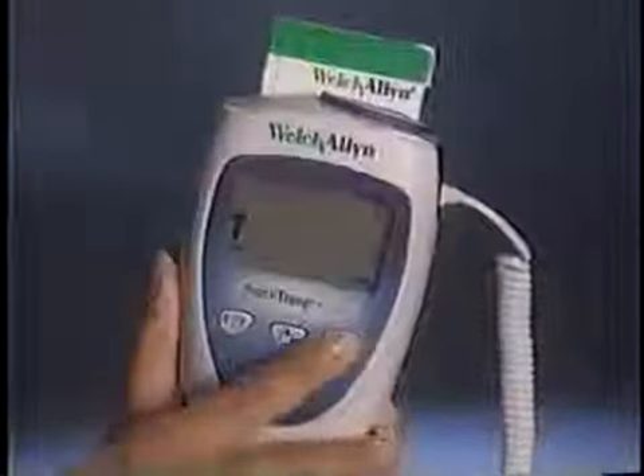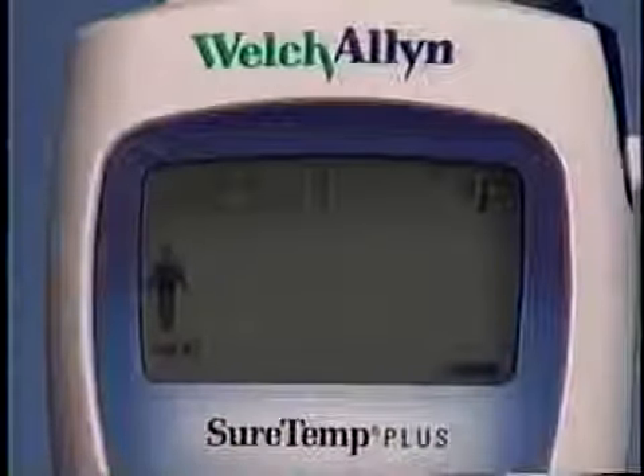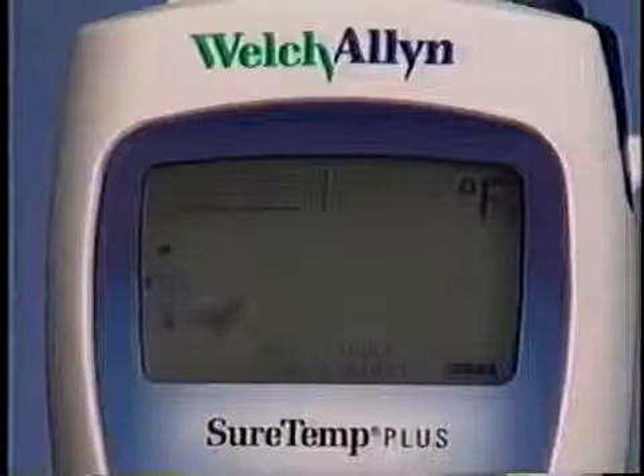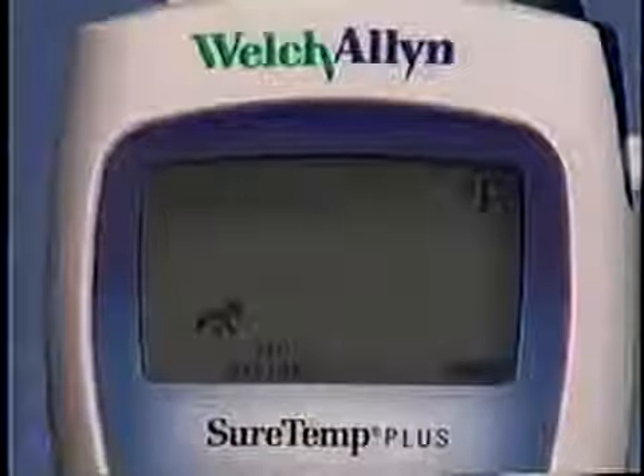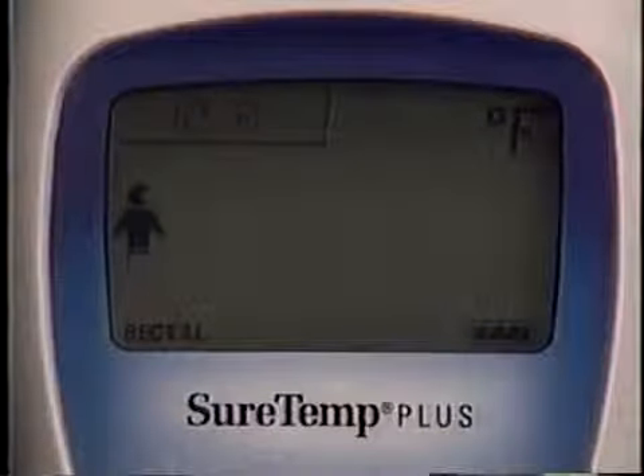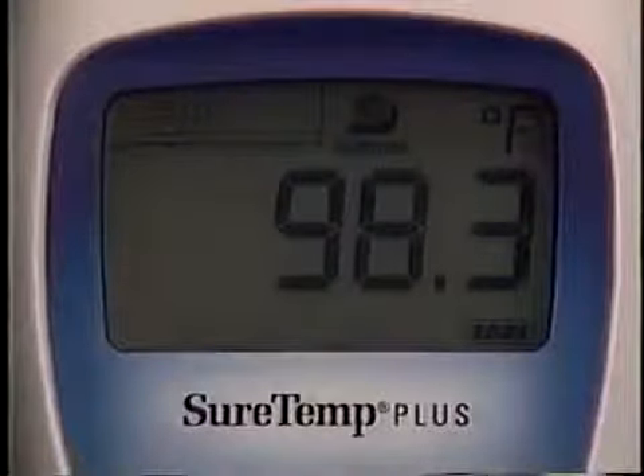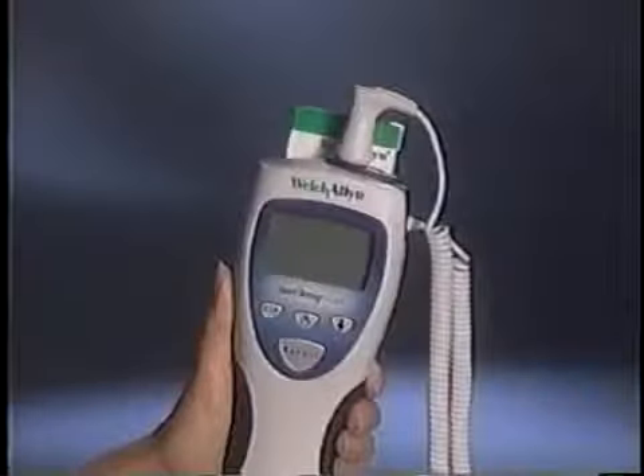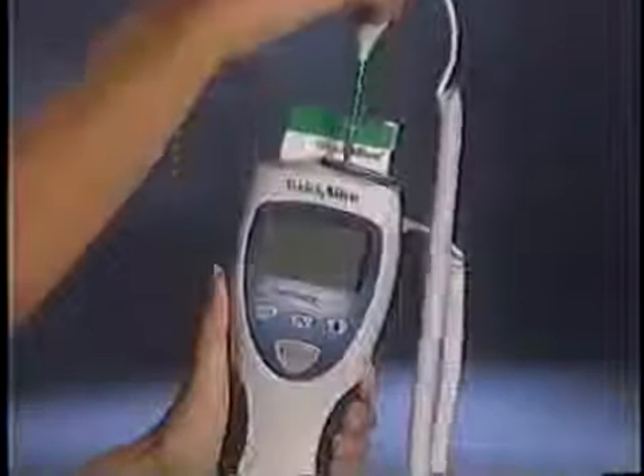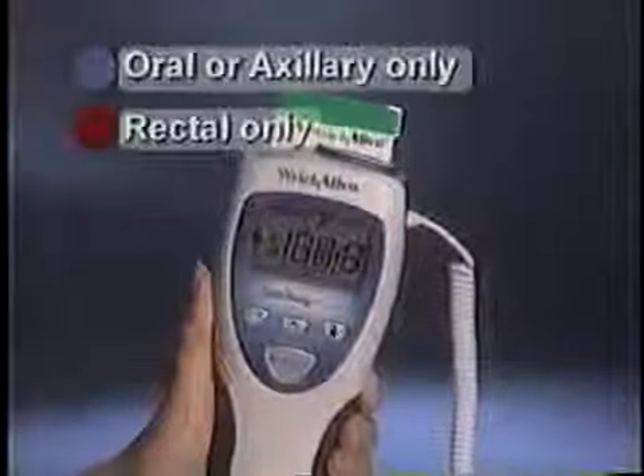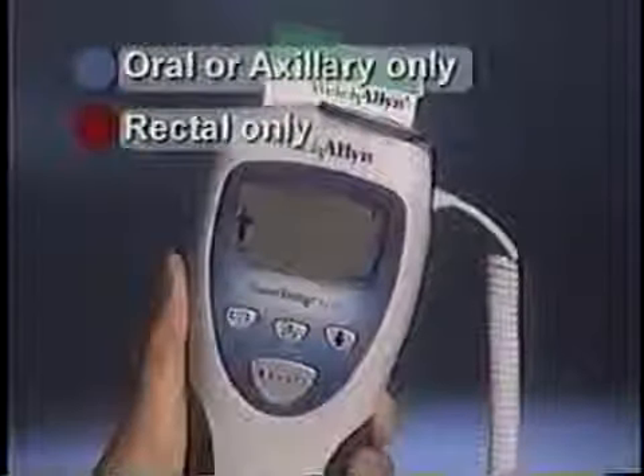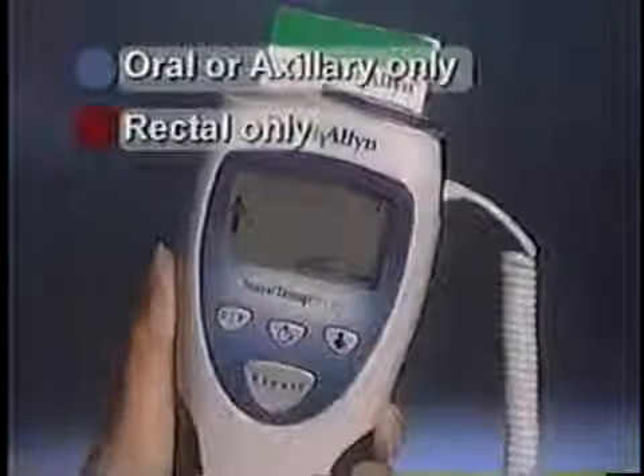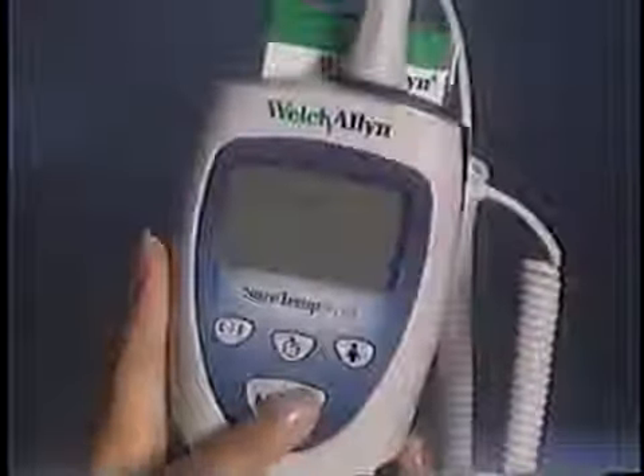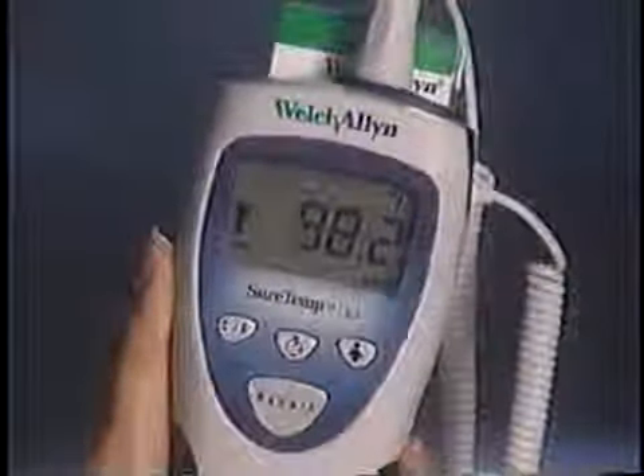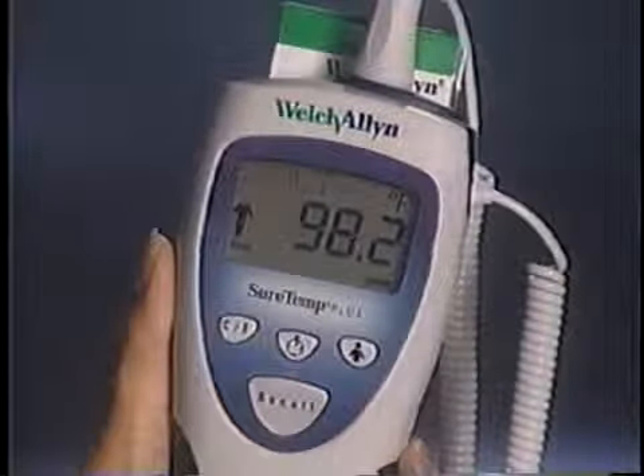The SureTemp Plus can take temperatures in oral, adult axillary, pediatric axillary, rectal, or monitor mode. Press the Mode Selection button after removing the probe from the well, but keep in mind the thermometer will only go into rectal mode when the probe with the red ejection button and red probe well are installed. Press the Recall button with the probe in the well to view the last temperature taken and the mode that was used.